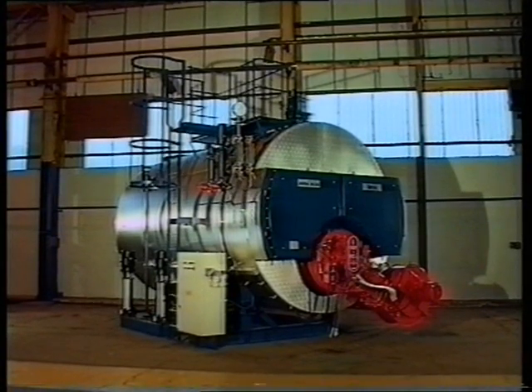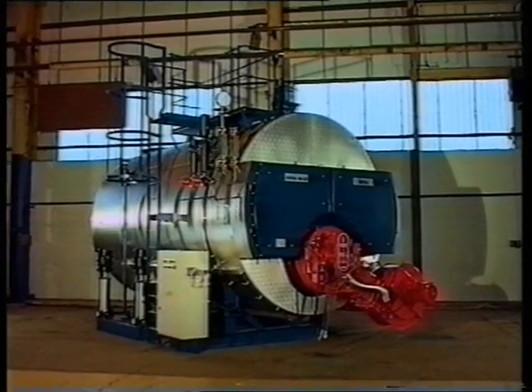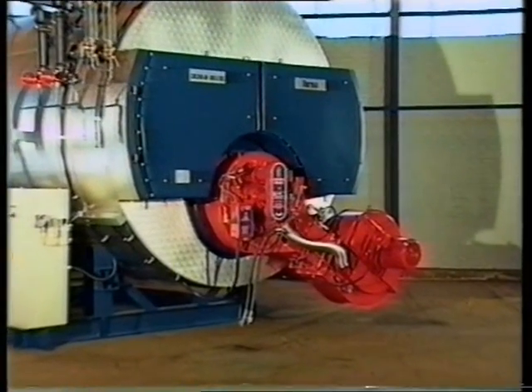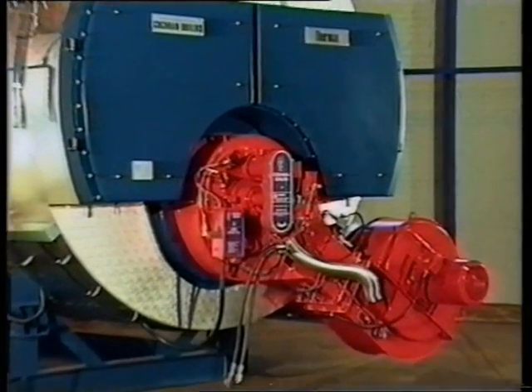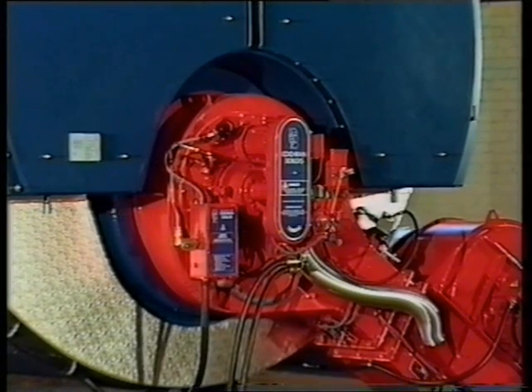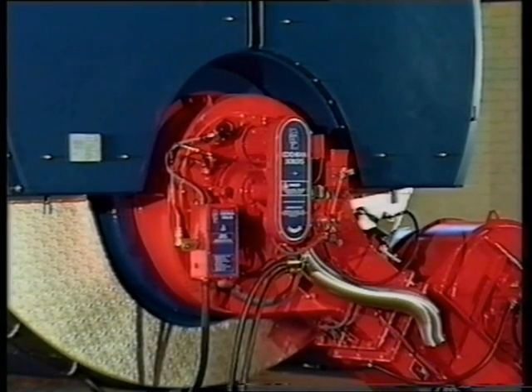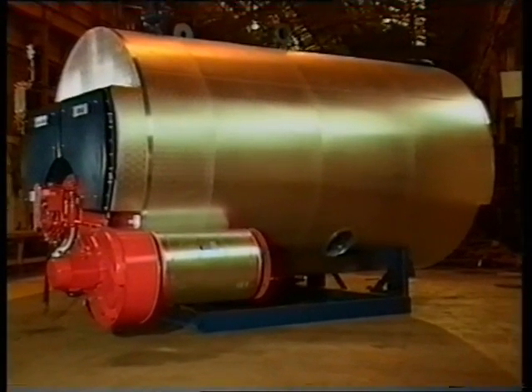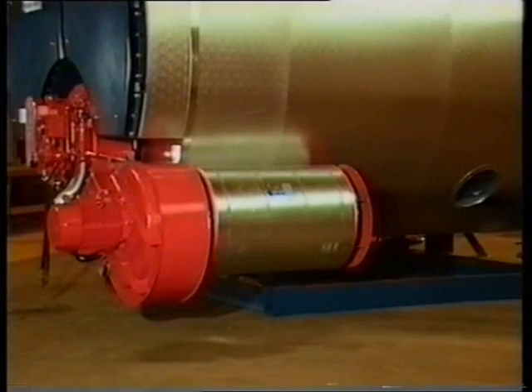The Cochran boiler is a package unit covering a range of evaporations and is of the three-pass wetback design. The first pass is the furnace and the second and third passes are nests of small bore smoke tubes. Welded construction is used throughout and designs are to the latest revision of British Standard BS 2790.